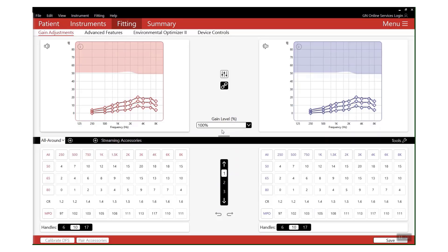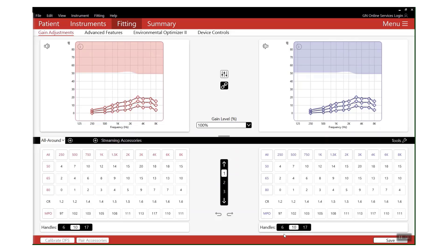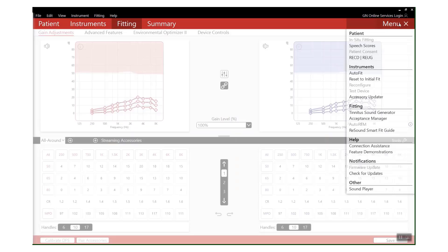Tip number two: use your Acceptance Manager. There may be several reasons why this can be useful for your patients. Firstly, due to our extended bandwidth, some patients, particularly first-time users, could find the sound to be just a little bit sharp in the beginning. Now what you could do is go into your gain handles and reduce those high frequencies, bring them back and increase as is appropriate. Alternatively, by clicking on Menu...